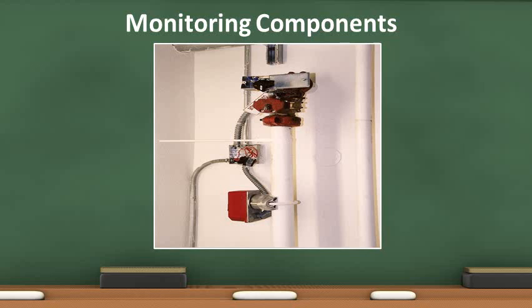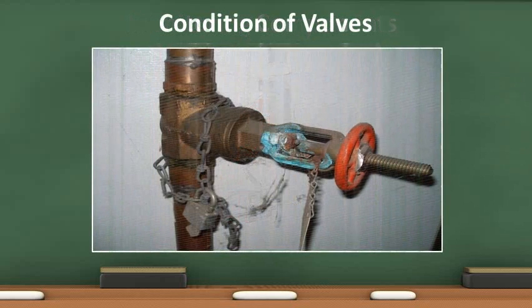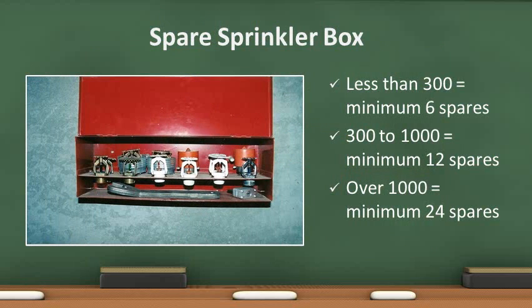Cover plates and conduit are required to ensure the alarm wiring will relay signals to the fire alarm panel. In this photo, the conduit is intact but the cover plates are missing. All valves are to be clean and in good condition. Corrosion may keep this shutoff valve from operating. All sprinkler systems are required to have a box with spare sprinkler heads and a wrench. The sprinklers shall be representative of the sprinkler heads currently in use in the system.